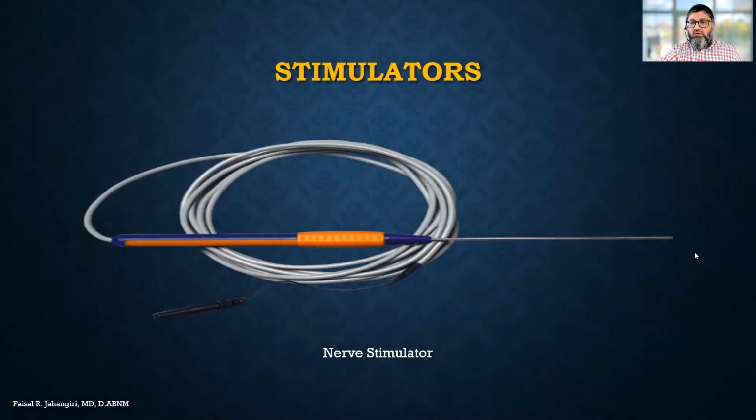This is the monopolar stimulator, which has either a fine tip or a blunt tip. The fine tip and blunt tip are used for peripheral nerve or cranial nerve stimulation. The ball tip is monopolar, so it is used as the cathode, and for the anode a subdermal needle can be used in the middle or nearby area or the contralateral side, depending on the type of surgery. So this will be highly sensitive, less specific.